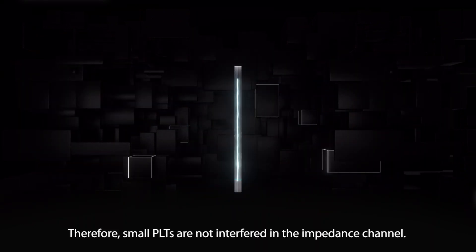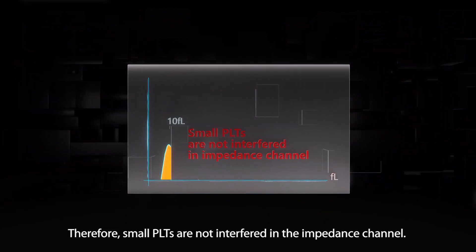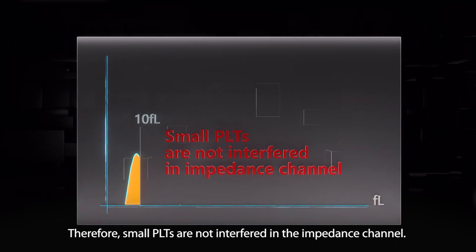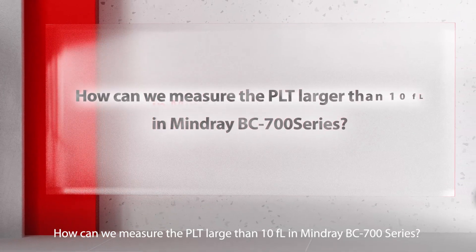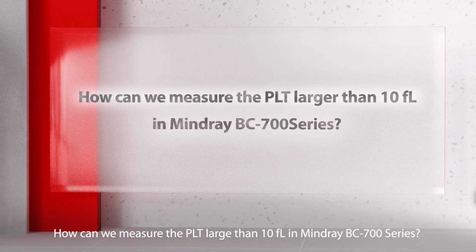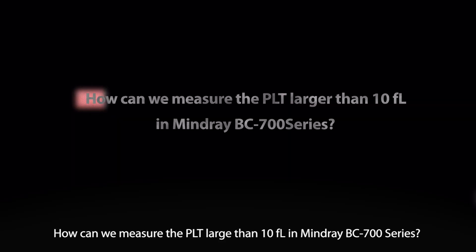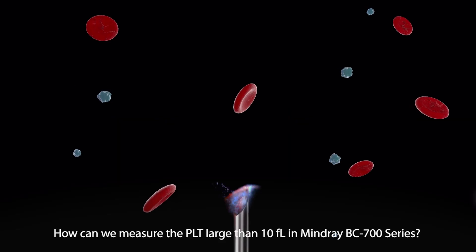Therefore, small PLTs are not interfered with in the impedance channel. How can we measure PLTs larger than 10 femtoliter in the MINDRAY BC700 series?